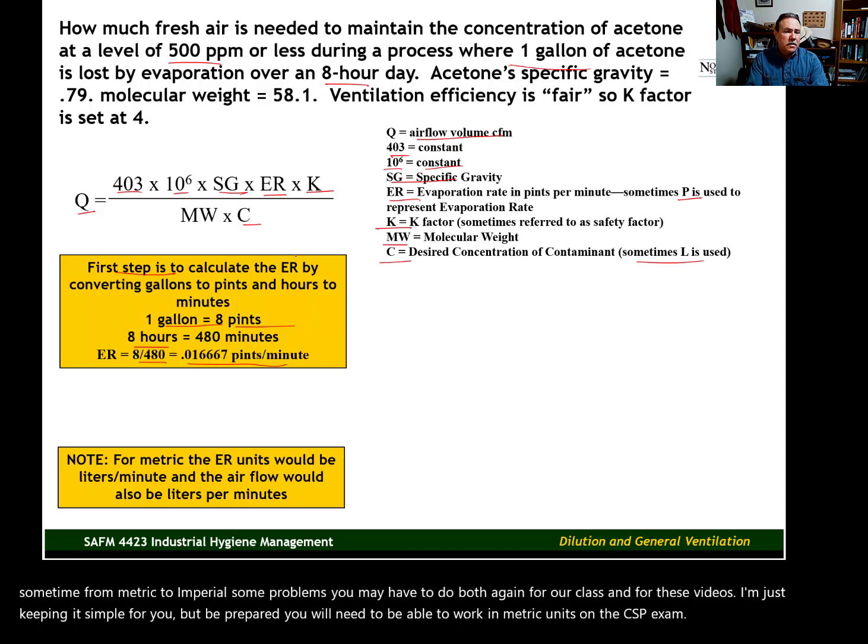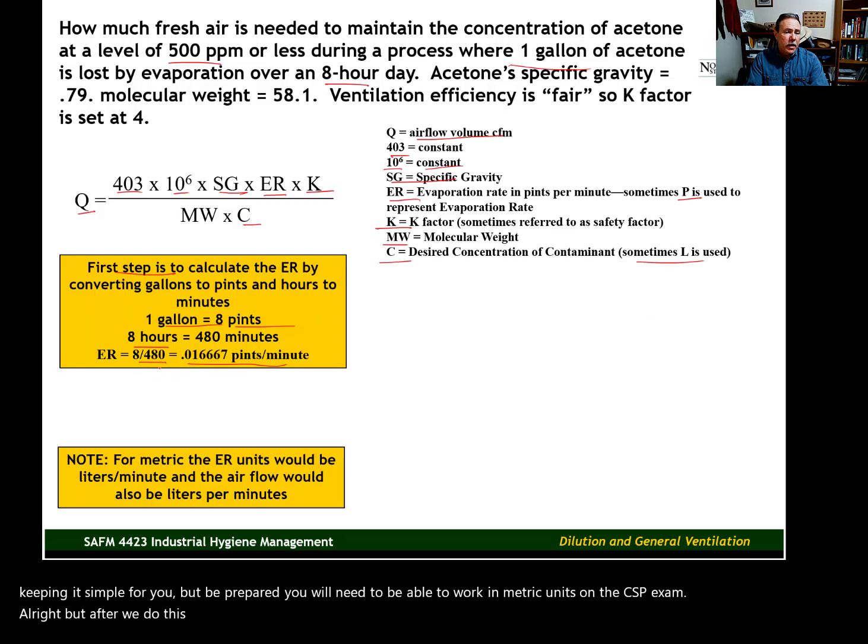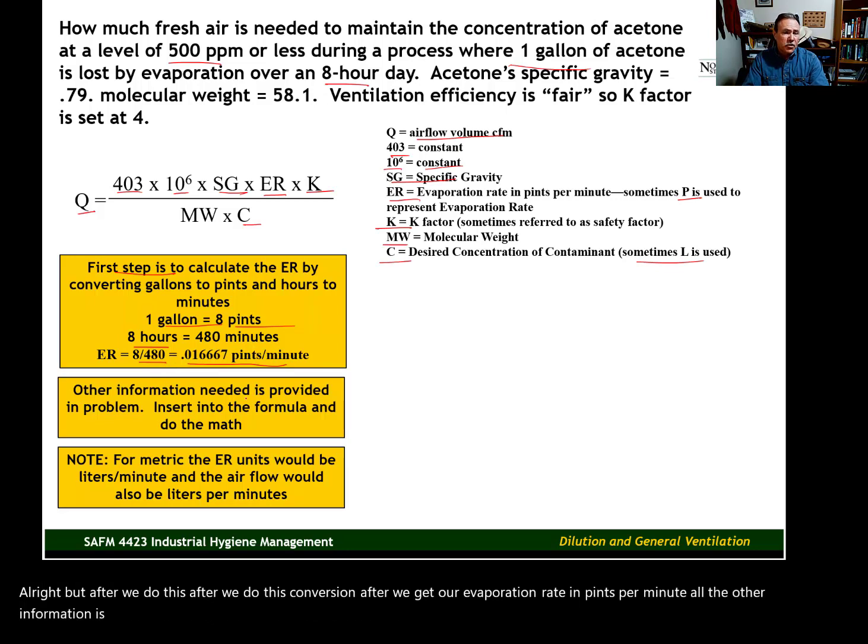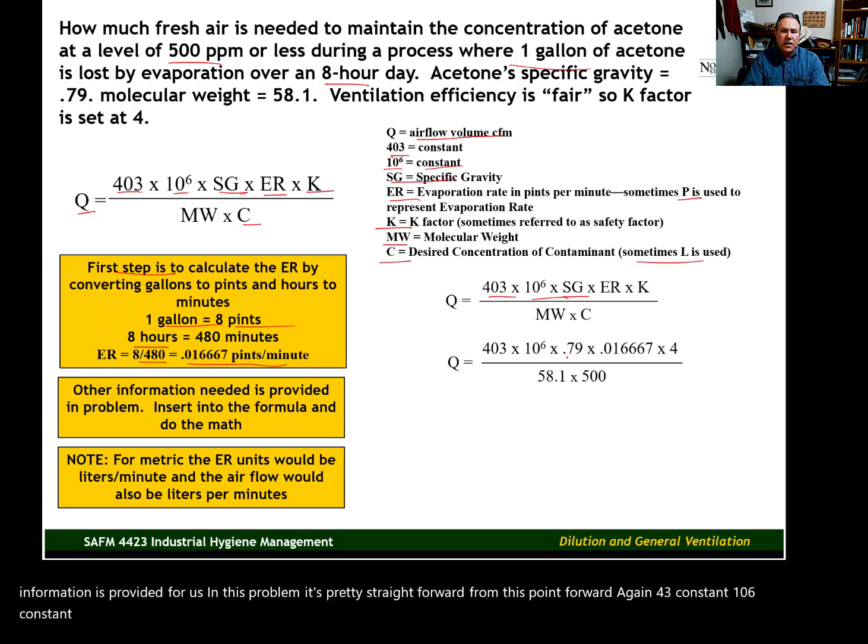All right. But after we do this conversion, after we get our evaporation rate in pints per minute, all the other information is provided for us in this problem. That's pretty straightforward from this point forward. Again, 403 constant, 10^6 constant. Specific gravity is 0.79. Evaporation rate is 0.016667, and you could get by with just rounding that to three decimal places if you want to. Then our K factor is given to us, and we plug that in. Molecular weight is given to us, and the desired concentration.